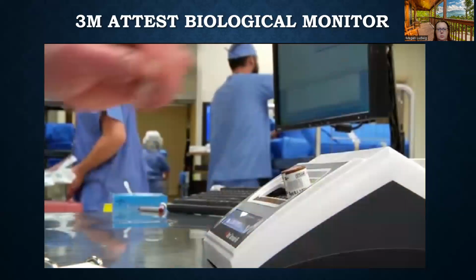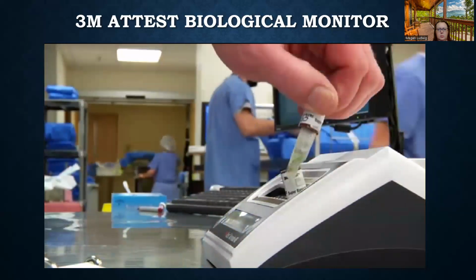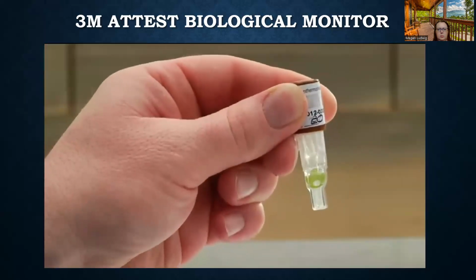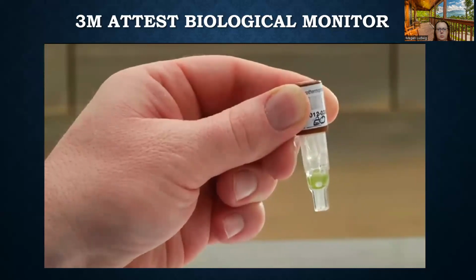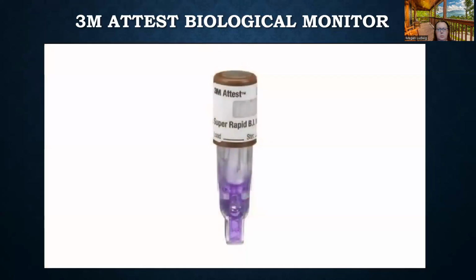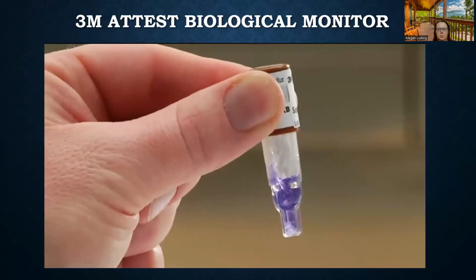In the case of a processed 1492V BI, a color change from purple to yellow of the growth media and/or non-woven material indicates a sterilization process failure. A negative pH color change result, where the media and non-woven material remains purple or blue, can be assessed after 48 hours of incubation.